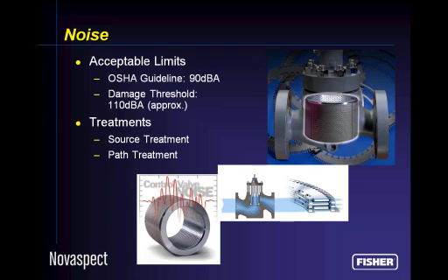Valve damage is something that occurs if noise levels are too high. Essentially, we convert valve noise to mechanical vibration, which results in parts banging around, and they wear out quite quickly. So even if your particular process doesn't seem to be too severely affected by any of those top three issues, OSHA, corporate practice, or good neighbor policies, I can guarantee you that your valve manufacturer is going to tell you when you're exceeding what we think is a safe noise limit for the health of the valve.